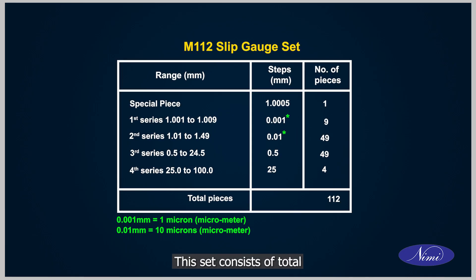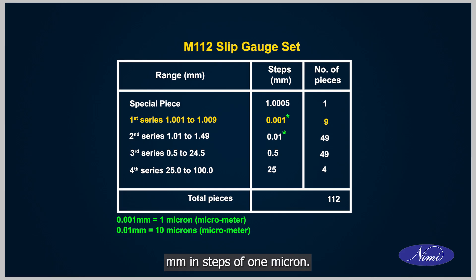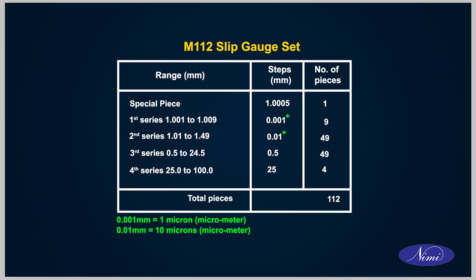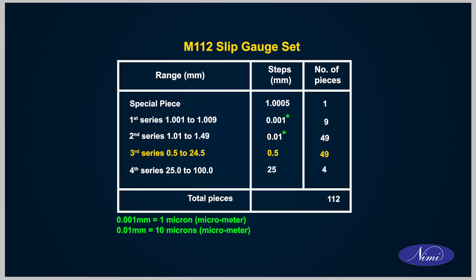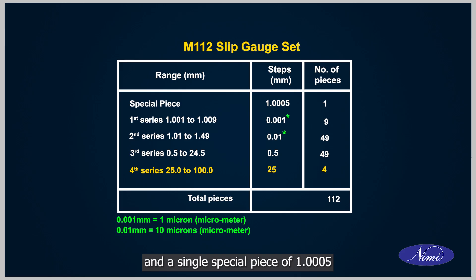M112: This set consists of a total of 112 pieces in 4 series with a special piece. The first series has 9 pieces from 1.001 to 1.009 mm in steps of 1 micron. The second series has 49 pieces from 1.01 to 1.49 mm in steps of 10 microns. The third series has 49 pieces from 0.5 to 24.5 mm in steps of 0.5 mm. The fourth series has 4 pieces from 25 to 100 mm in steps of 25 mm, and a single special piece of 1.0005 mm.